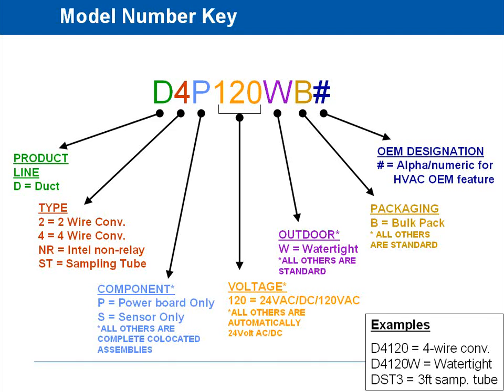If you have an S, it's a sensor-only board. If you have a P, it's a power-only board. If you have nothing, then it's a traditional detector, which has the sensor and the power combined, like I showed you before. If it says 120, it's 120 volt. If it says nothing in that spot, it's 24 volt. If it says W, it's the outdoor NEMA 4 watertight version. If it doesn't say W, it's just a regular smoke detector.